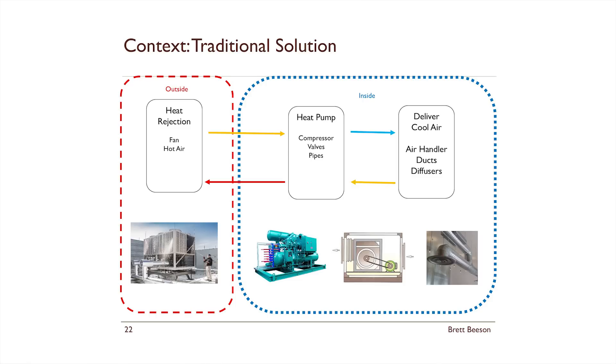So this then leads to all the stuff you need to coordinate in the building. So you've got a cool fluid, you can put it through pipes with lots of copper, you can blow air over it. So now you've got cold air, which is a good start. You've got to get the air to the occupants. So you have big ducts, typically for the buildings you'll see in the city. They might be one, even two metres in diameter to get that volume of air down. So that's a big impact on your floor plate that you need to plan for. Then they'll go into each floor, branch off into a whole lot of smaller ducts, a bit like your lungs or circulatory system and eventually get into diffusers, which blow that air down onto you at about 12 degrees, gradually heats up with all the loads, goes back up into another set of return air ducts at about 24 degrees.